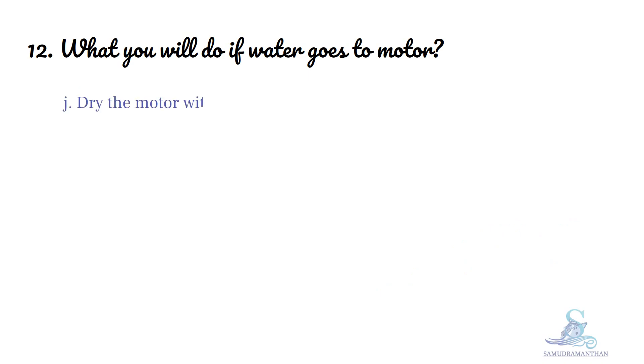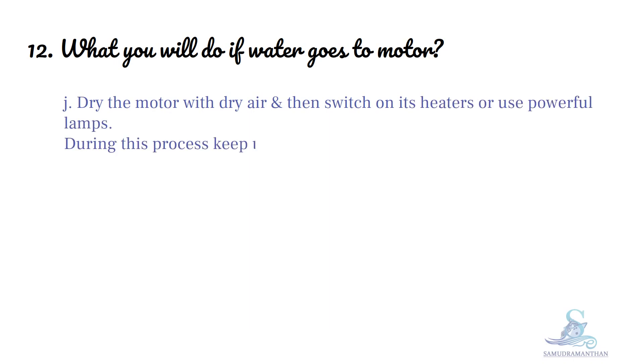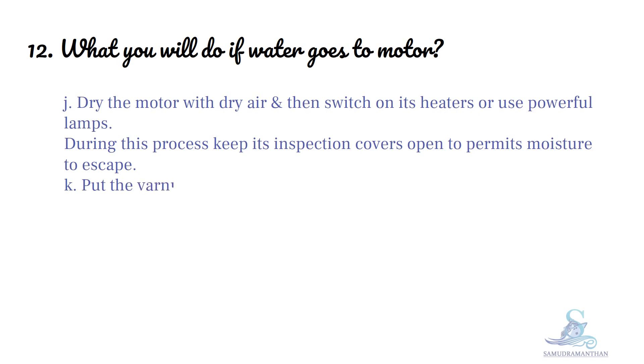Then, dry the motor with dry air and then switch on its heater or use powerful lamps. During this process, keep its inspection cover open to permit moisture to escape. Put the varnish on the windings and let it dry.